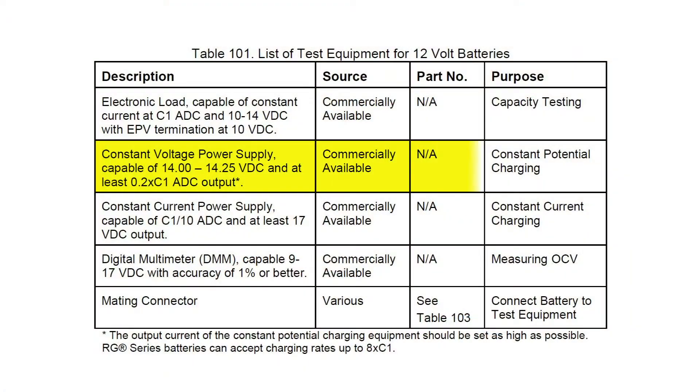The charging equipment for a constant potential charge must meet the requirements given in Tables 101 or 102 of the CMM. Table 101 is for 12-volt batteries and Table 102 is for 24-volt batteries. As seen in Table 101, the charge voltage must be 14.0 to 14.25 volts and the output current must be at least 0.2, or 20%, times the C1 rating of the battery.